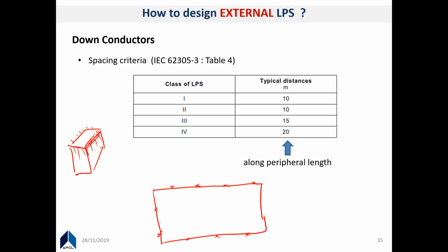There are concerns when you cannot just bring them down wherever you want. So the distance which I mentioned is this one. As you go along class 1 to class 4, your allowed distance increases, meaning you can have more separation between down conductors, meaning you can have a lesser number of down conductors along the periphery. Let's say your total peripheral length is 100 meters, and your span is like 20 meters.